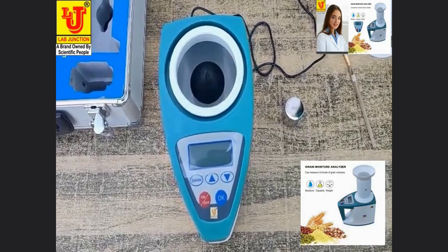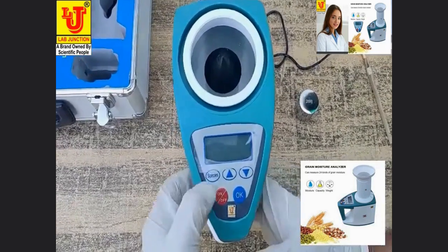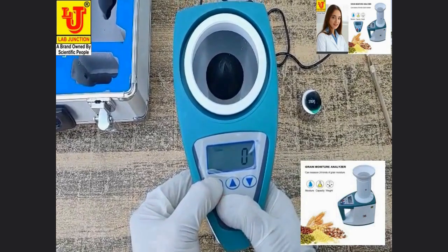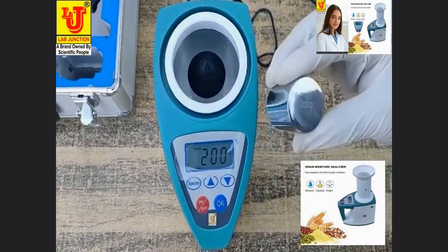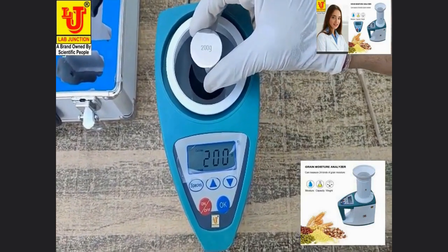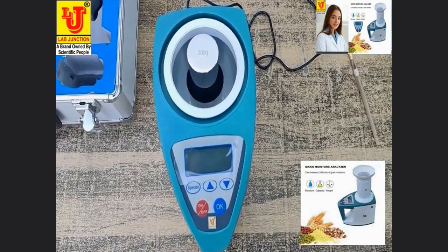Doing calibration of the grain moisture meter. For calibration, first press the species key and switch on. It shows 200 grams. Now take this weight of 200 grams, put it on the sensor, and press OK. Calibration done.